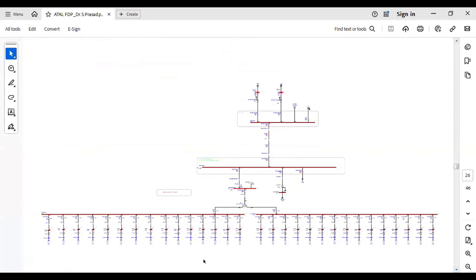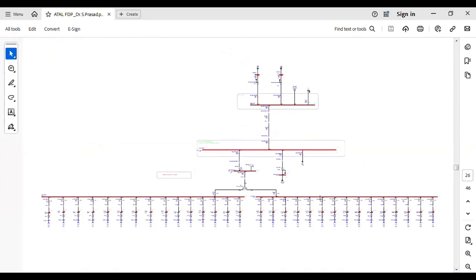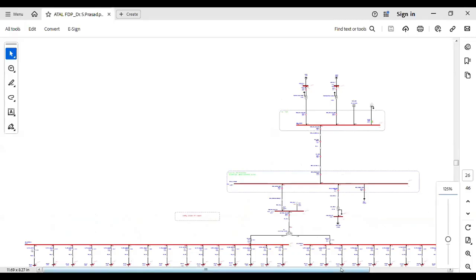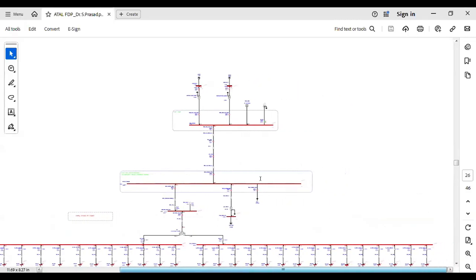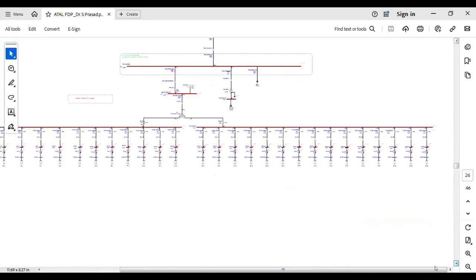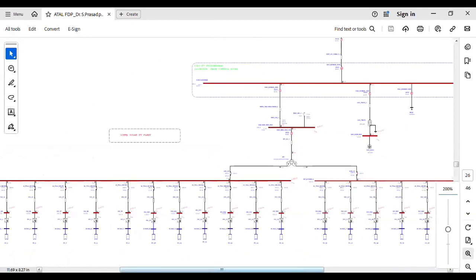Because the rating of the circuit breaker will be decided based upon the short circuit test, we need to check at the LT panel. Suppose at the two LT panels, because this is a three winding transformer, you need to see how much short circuit current is flowing. So let me show you.